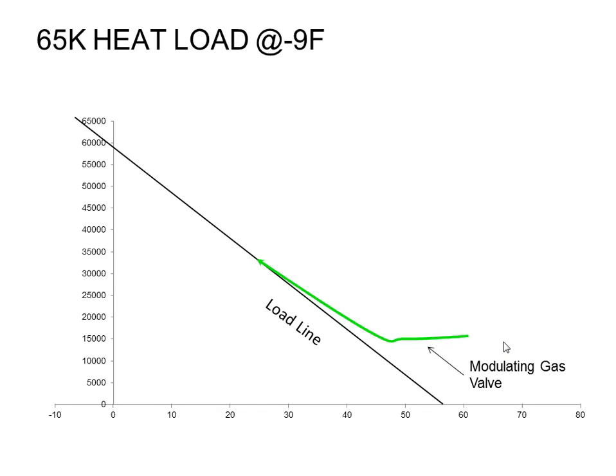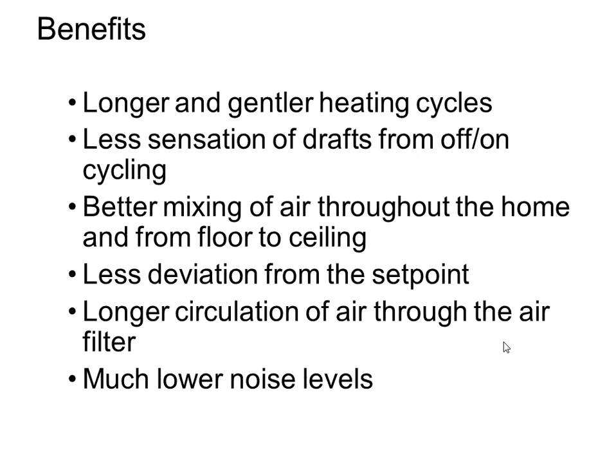Same thing happens with this gas valve. I can give you X amount of therms all in big blasts, or I can let it trickle out through the gas valve all day. Either way, you're buying the same amount of therms. Which one's more comfortable? Which one do you think the plants like better? I'm pretty sure most plants would rather have the soaker hose than a big puddle of water piled on top of them for 5 minutes. Same thing happens with the comfort of your building owner or your homeowner. I think they'd rather have the consistent discharge air temperature than 125 degrees blasting on them, then 65. That's kind of the story with that.